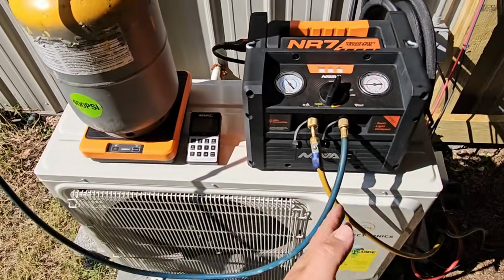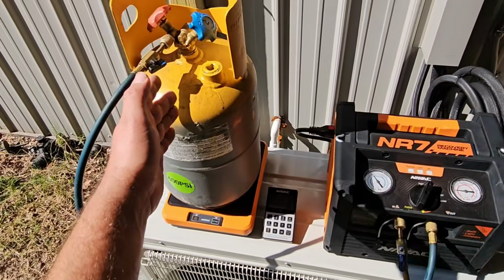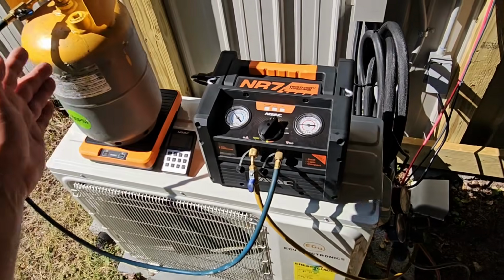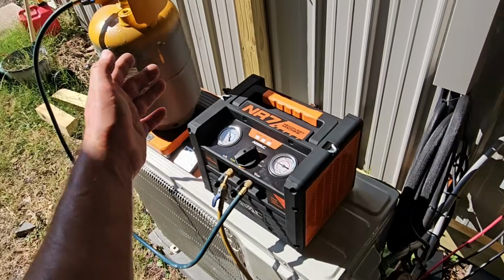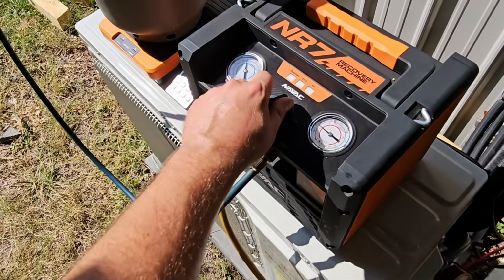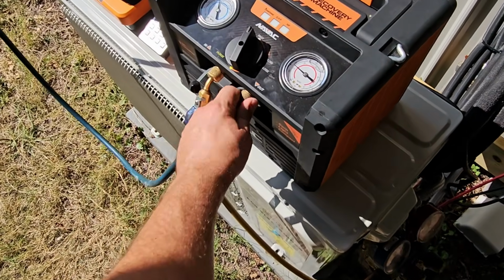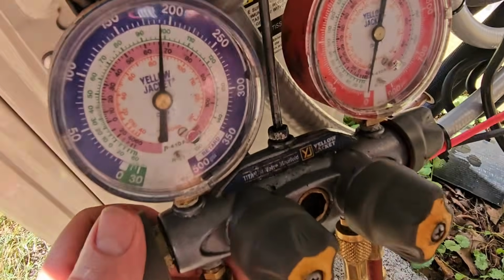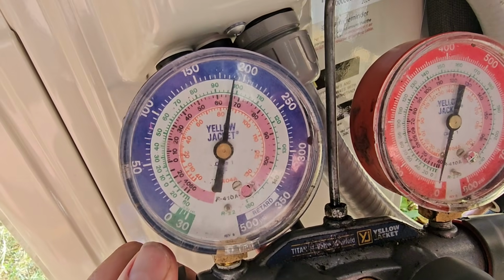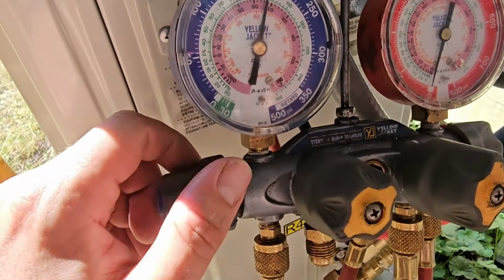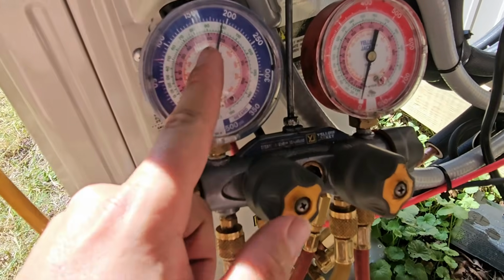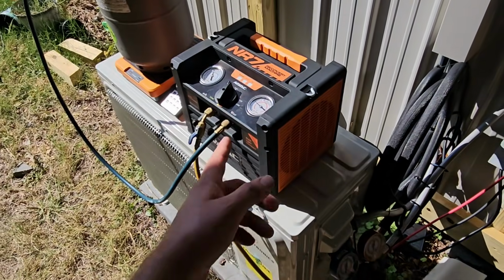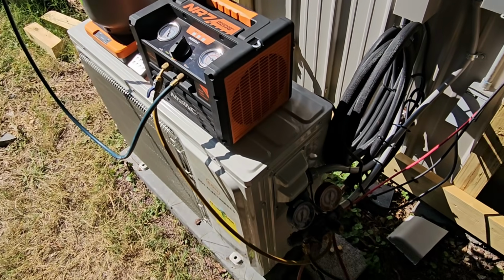And since the pressure's higher in the system than it is in the tank, it's going to equalize. So we're going to be able to pull out some of that refrigerant without actually turning on the recovery machine. So that's nice. So you can see what's happening. See? Pressure is going down. We're going to do this until it stops, and then we're going to turn on our recovery machine.